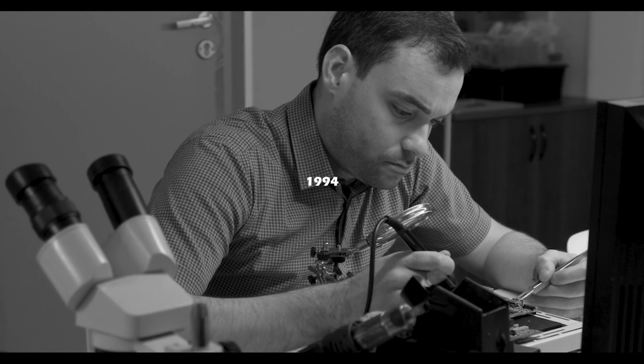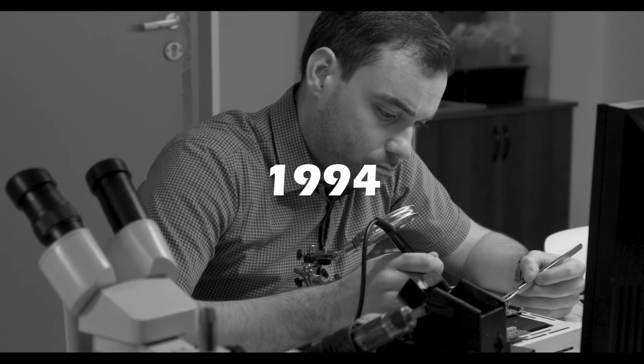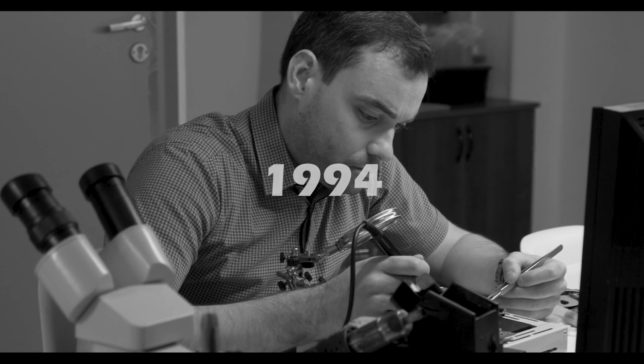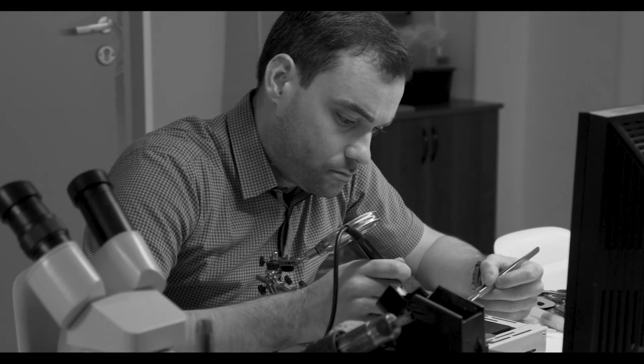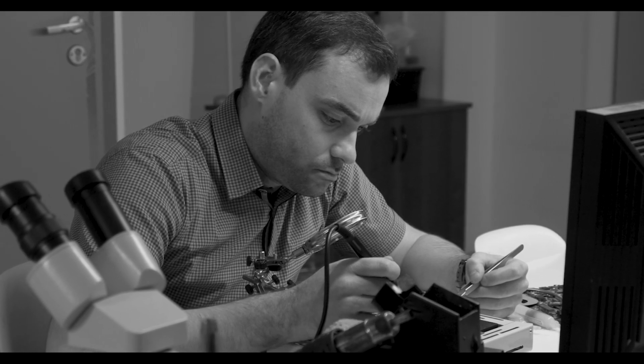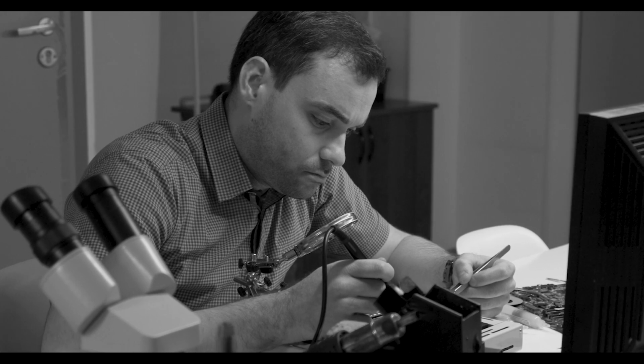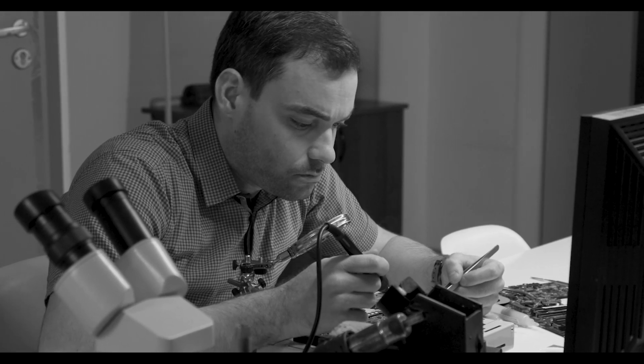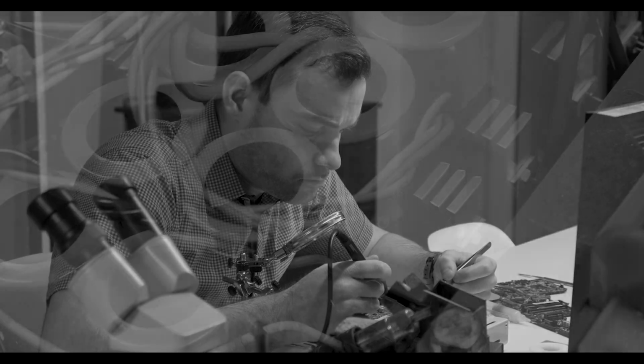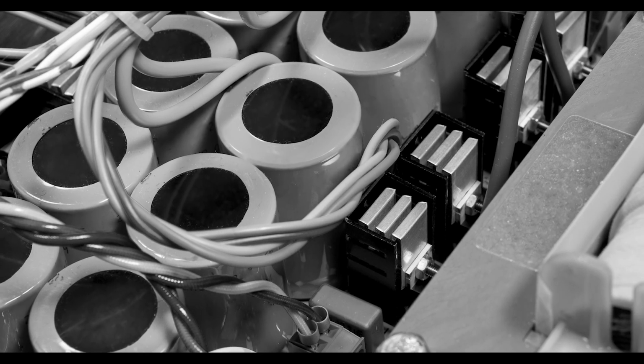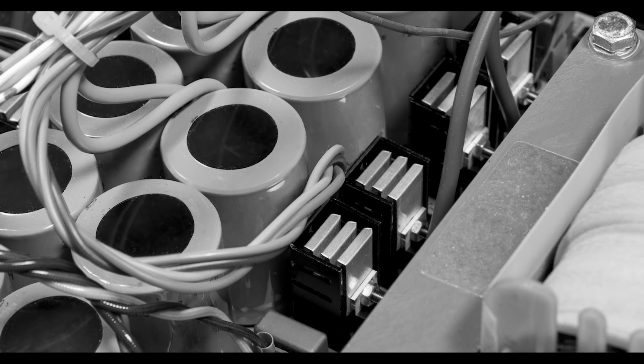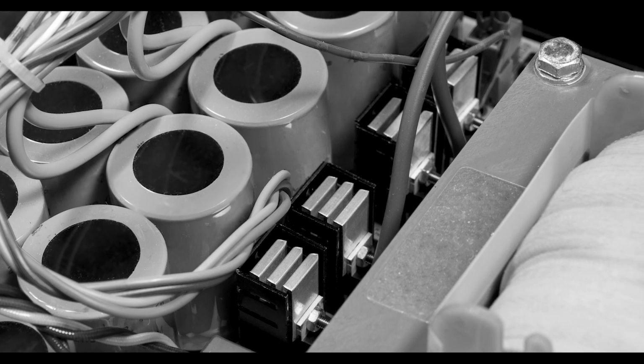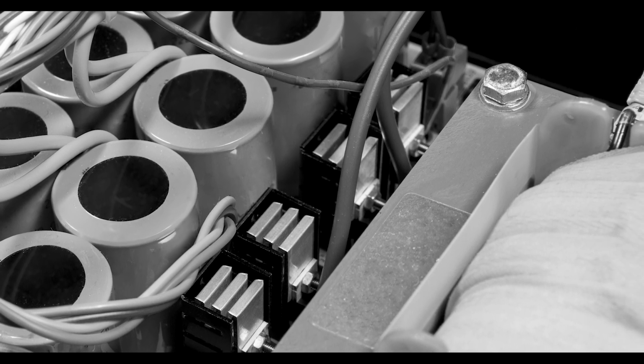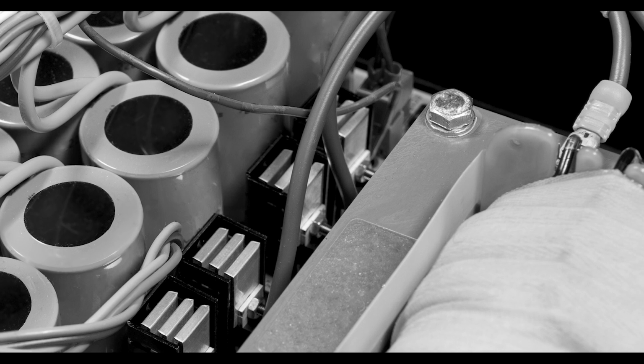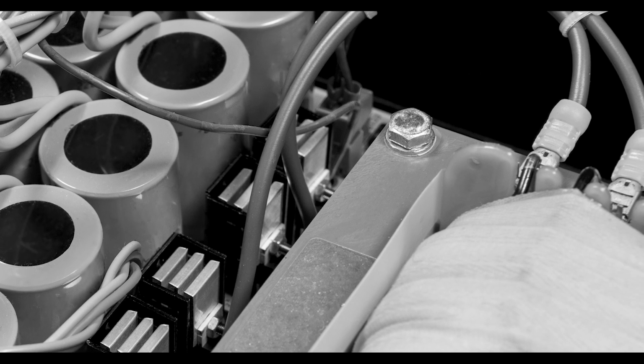30 years ago, all of the major inverter manufacturers in the US used heavy-duty, low-frequency, iron core, copper-wound transformers in their inverter designs. These classically trained engineers understood the value of using a low-frequency, iron core transformer because of its ability to provide a far longer life expectancy, a much safer product, and a superior peak power capacity for starting high inductance loads, such as refrigerators, microwave ovens, AC units, and power tools.